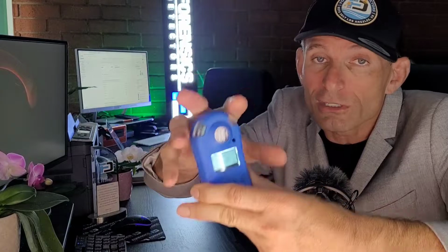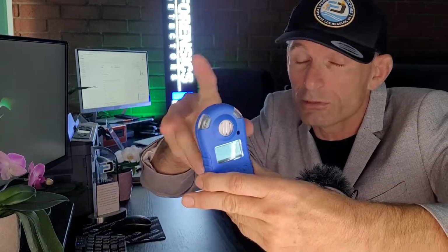Just make sure you're confident and you're not going to exceed 100 ppm. If you think you will exceed 100 ppm, folks, get one that's 1,000 ppm. Make sure you have enough headroom, okay? Otherwise, you're going to poison the sensor. Then I get the call saying, Dr. Kaz, I think something's wrong. It's not working because we've exposed the sensor to higher levels than 100, okay, folks? You see what I'm talking about? If you're confident you're within 0 to 100, get the 0 to 100. If you think you're going to go over and there's that small few percent chance, please get a higher range. Email us and we'll custom build that for you, okay?